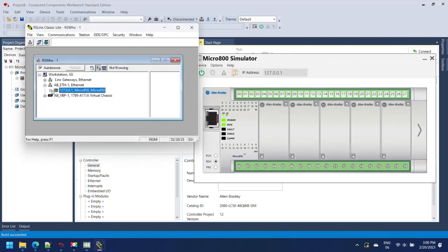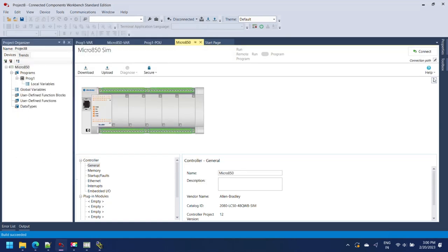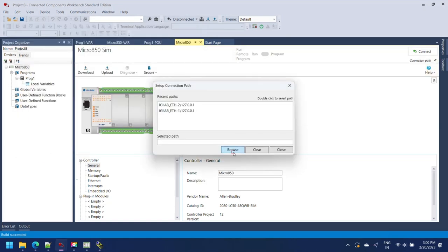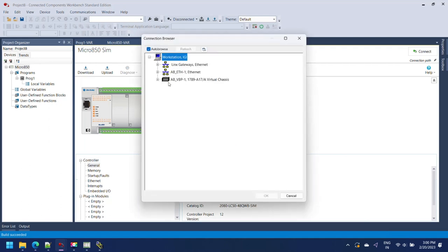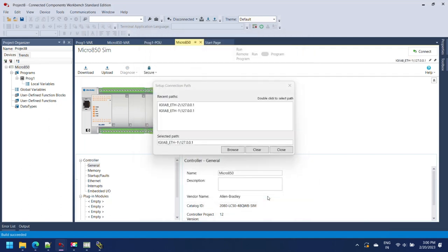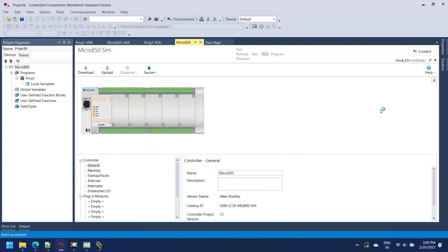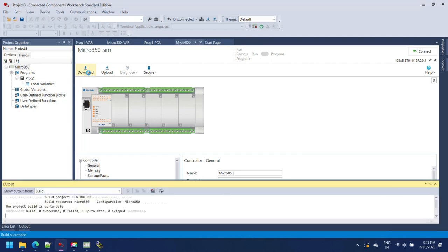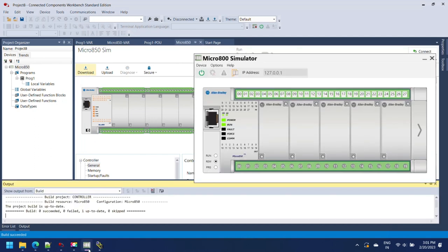Set path for simulator in Connected Component Workbench. Open your project and go to Micro 850 property and set the path of simulator. Click Connection Path, a Windows Setup Connection Path will open, browse your simulator. Download your program to your simulator and change simulator to remote mode then start your program in simulation mode.